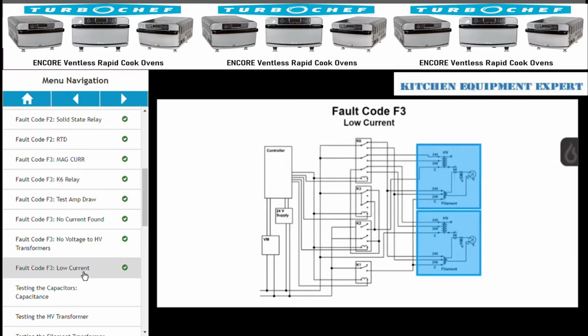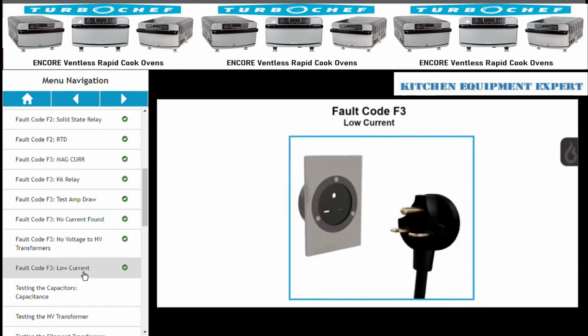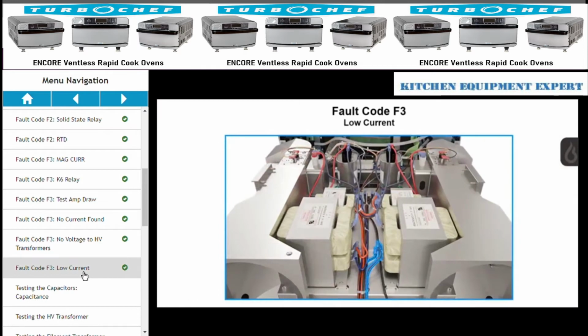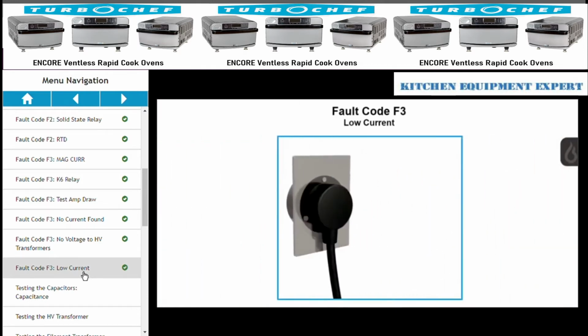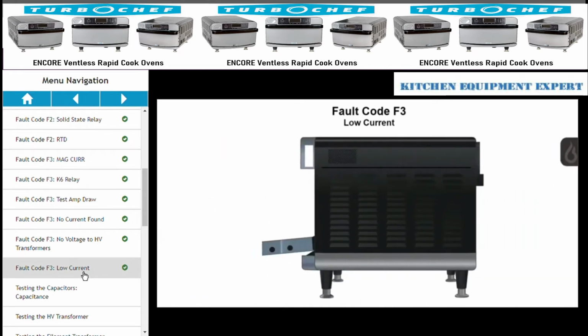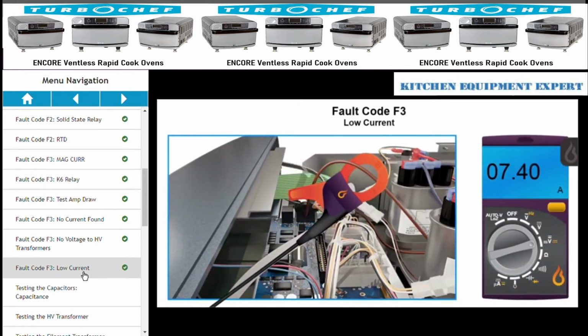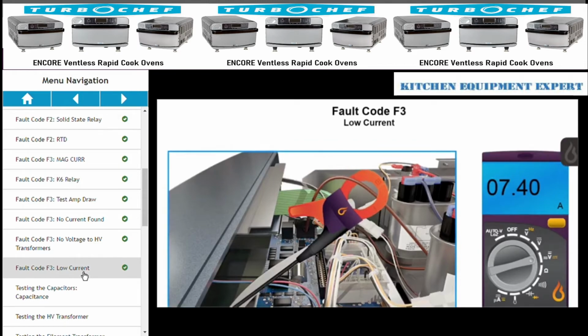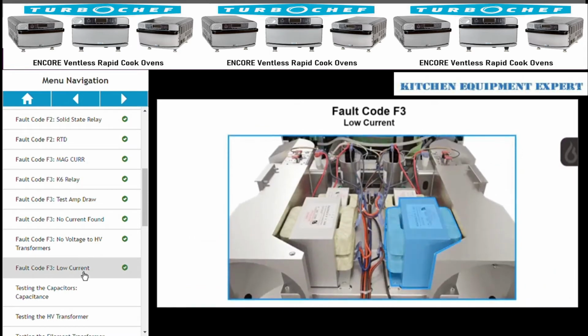To decide which one is the problem, unplug the oven and remove all 3 wires from the primary of one of the transformers. Plug the oven back in, and refresh the load in the oven. With your amp clamp set to AC amps, on the brown wire start another cook cycle. If you see the same low amperage reading, the problem is with the side you disconnected. If you get no current reading, the problem is with the other side.